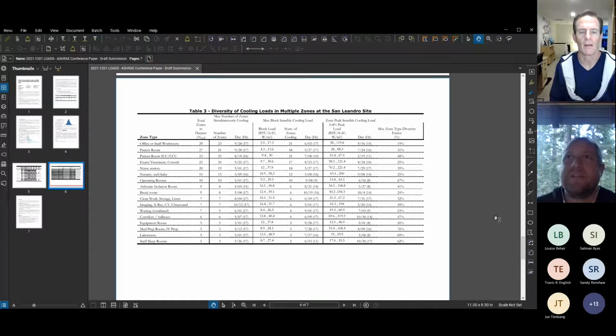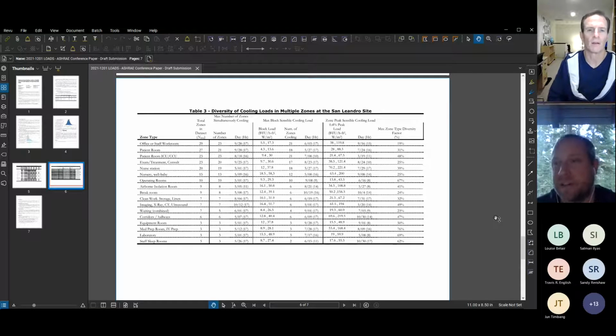There's a net cooling to that space, and we're measuring that value. We're not measuring directly what the air handler is supplying to the box and what the reheat is. We can measure the valve position, et cetera, but we're not measuring the two pieces independently. But if you total this up and call it tons, then it's potentially understated, right?